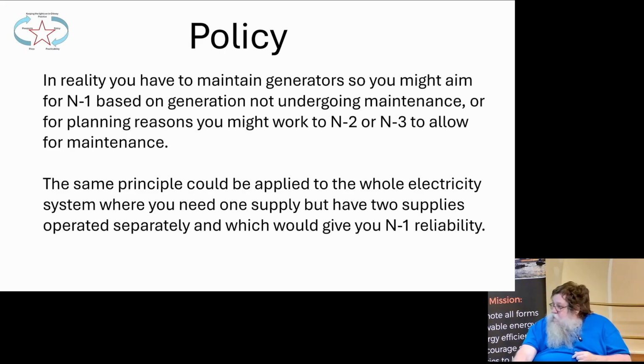So in reality, you might have to maintain generators. So you need more than the generators that you're actually using to provide the load, so that you can have one that you're doing a repair to, or you can allow for one breaking down. And we could apply the same principle to the whole electricity system, but we don't.